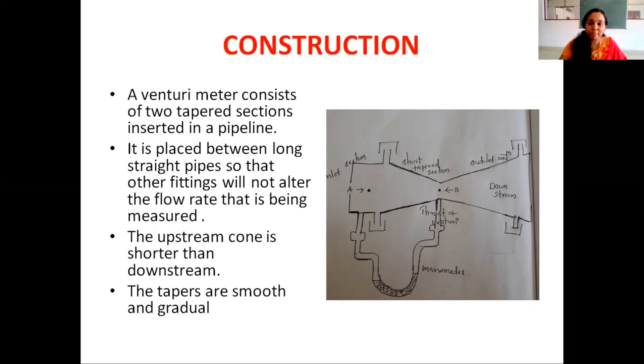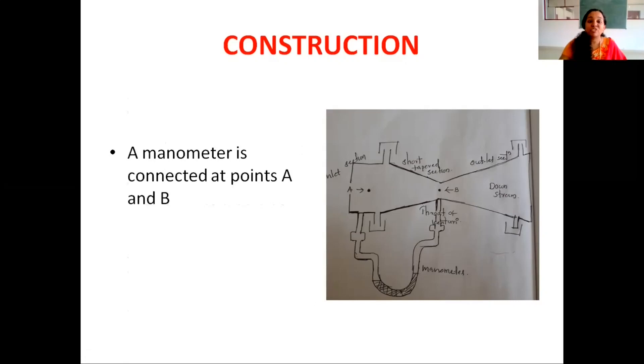Moving on to the construction of Venturi meter: it consists of two tapered sections. In between these two tapered sections, there is a narrow constriction known as the throat of the Venturi. This is the upstream section and this is the downstream section. The upstream tapered section is short compared to the downstream section, and this device is placed between a long straight pipeline. A manometer is connected between two points A and B, and is used to measure the pressure variation in the upstream.